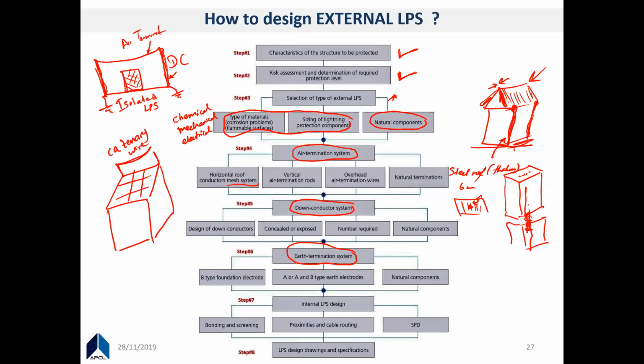So the natural components, and the next one is a down conductor. We'll be designing down conductors and determining the number of down conductors required under the same design, and whether they are concealed or exposed. Beyond the number game, these are facts you have to consider, whether your down conductor is to be exposed or concealed, because architects often don't prefer down conductors being shown to viewers passing by. They need them concealed, meaning hidden. As a solution, you can go for natural components, like having a separate or additional down conductor in the columns.